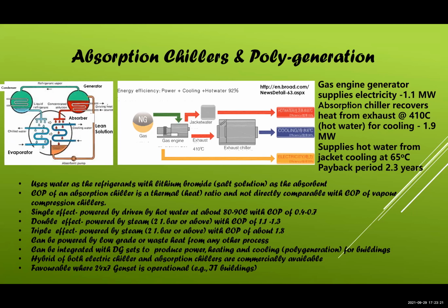Therefore, electricity requirement is very, very marginal compared to mechanical vapor compression, and it uses heat rather than electricity. So you can't really compare COP of absorption with COP of mechanical vapor compression systems. And now you can buy double stage absorption chillers with 1.2 COP or triple stage with 1.8. And these are all commercially available, and they use water and lithium bromide.